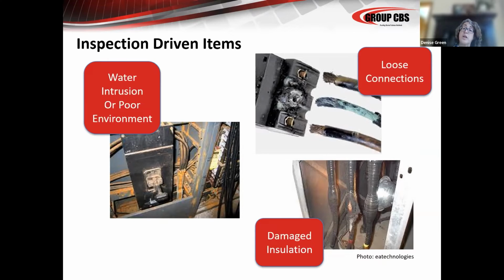I'm sure you've all seen loose connection situations. That's a maintenance concern. When you're maintaining, especially molded case and insulated case breakers, at some point those cable connections are checked. It's especially important, between 6 months and a year after a new installation, to make sure that those initial installation connections are still tight, and those are backed off and retorqued to verify that nothing loosened after everything settled and sat there and had that 60 hertz hum going through it, so that you don't end up with any loose connections.